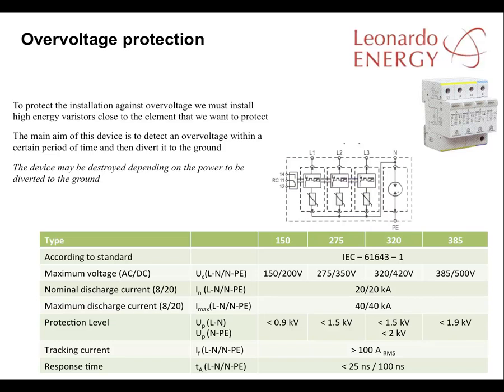To protect the insulation against overvoltage, high-energy varistors must be installed close to the element to be protected. The main aim of the varistors is to detect any overvoltage quickly and then divert it to earth. The varistor may be destroyed in the process, depending on the level of power to be diverted.